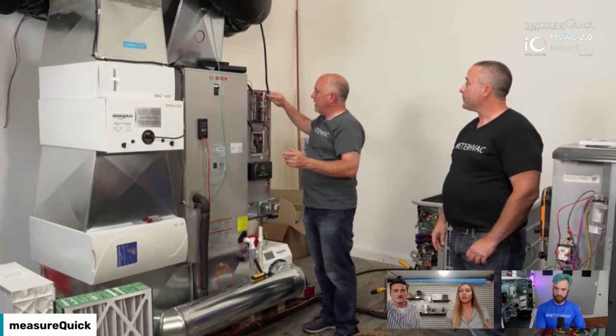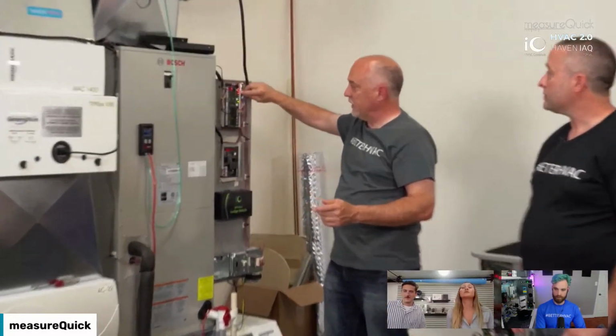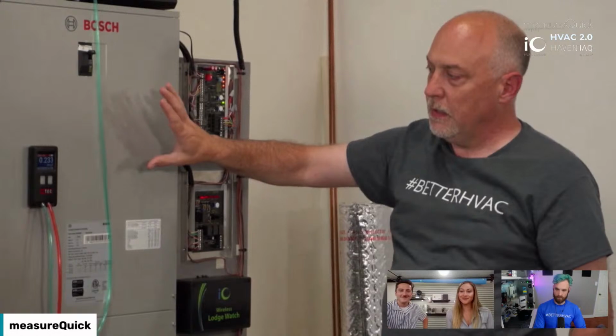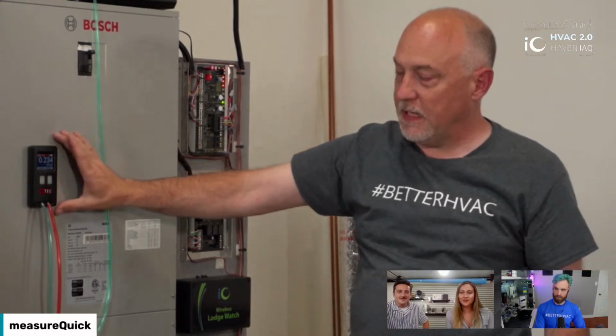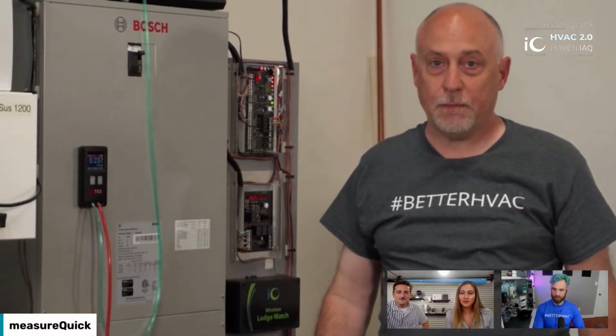Yeah, we're on Y2 right here. So this is sort of nice too - we also get all the calls for heating and cooling. So we've got the fan on, we're on the highest fan speed, and we're running 2.3 inches of static pressure, total external.